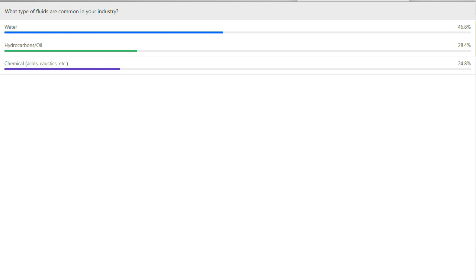Mostly water, the hydrocarbons and oil. I've got to admit that most of the applications that I do are for hydrocarbons and oil. Water is a particularly tricky substance. It's a great substance to pump as long as the temperatures stay low. But once water gets above 250, 300 degrees, it becomes a very difficult liquid to pump. The pressures get tremendous, the vapor pressure of water. You must keep it at a very high pressure in order to keep it in a liquid state. It also loses all of its lubricating properties that water is known for. It wants to flash into steam at a moment's notice, and so it becomes a very difficult fluid to work with at higher temperatures.